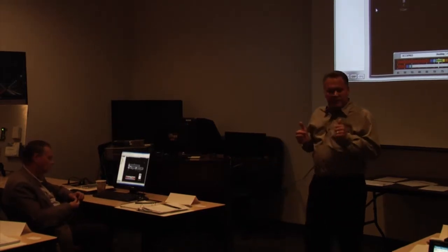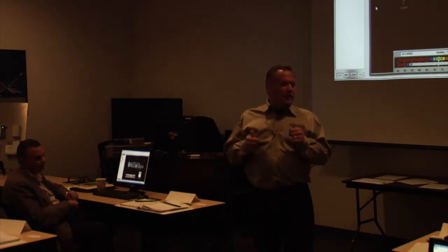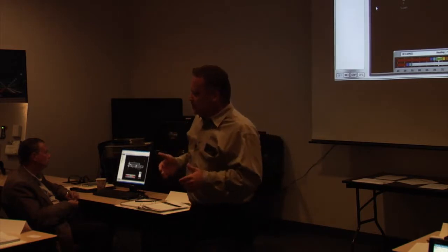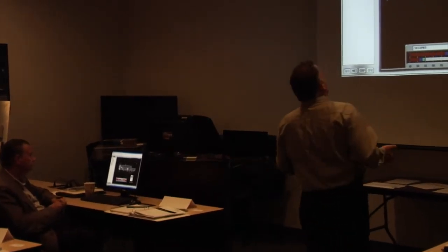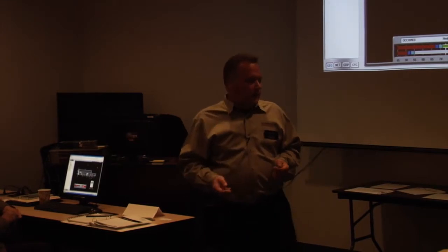So we're going to set this air handler up on our screen so that when we look at it, it looks right, the way that an air handler should be running, right? We're going to have a return temperature around 72. We're going to have a discharge of like 55, all right? We're going to get all this working. Our outside air dampers should be 20% open unless we're doing return CO2. We're not, so we have to go to a 20% minimum on our outside air, all right?